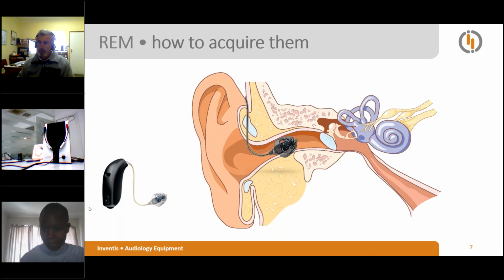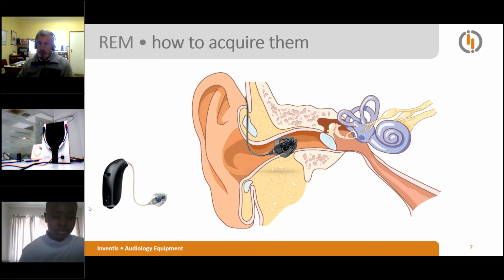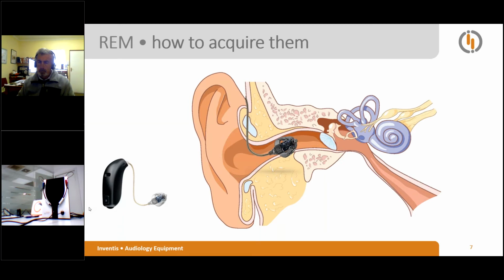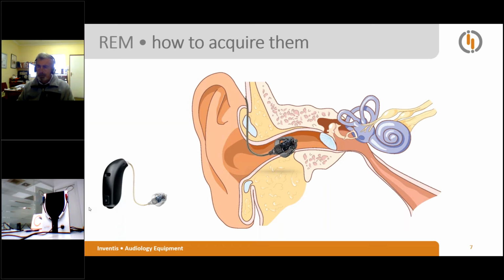So, a real ear measurement system allows the hearing care professional to accurately measure the performance of a hearing aid directly in the patient's ear canal. The acquired measurements show the real sound pressure level, the intensity, produced by the hearing aid at the patient's eardrum, and so allows the hearing care professional to adjust the gain of the hearing aid to meet the patient's need.